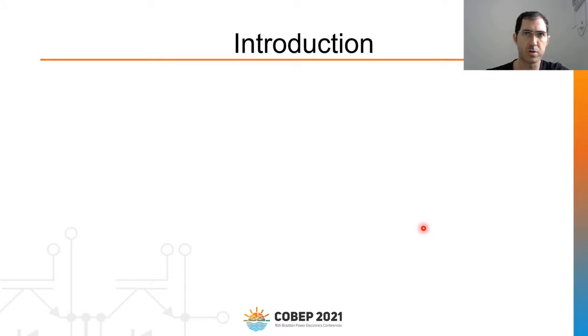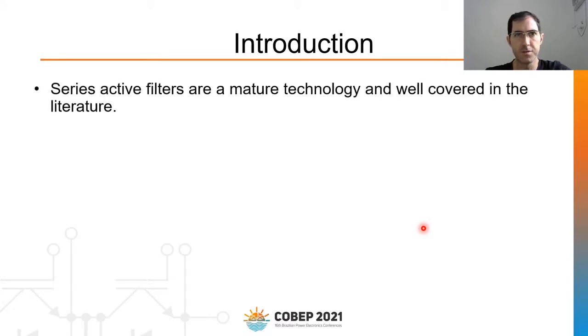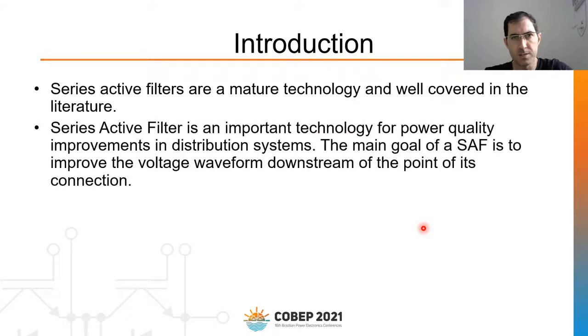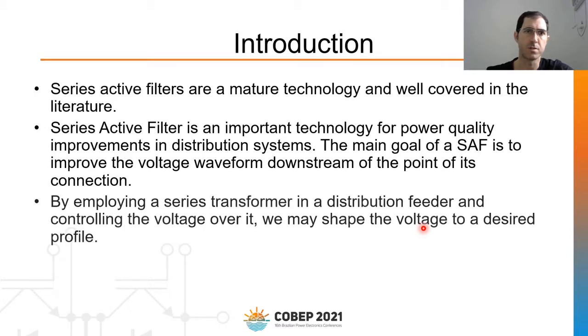Let's start with a short introduction. The series active filters are a mature technology and well covered in the literature, and series active filter is an important technology for power quality improvements in distribution system. The main goal of a series active filter is to improve the voltage waveform downstream of the point of its connection. By employing a series transformer in a distribution system, and controlling the voltage over this transformer, we may shape the voltage to a desired profile.